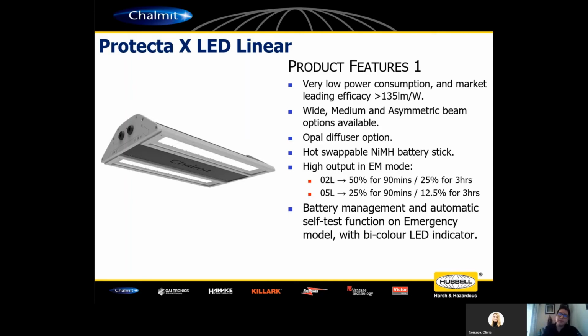The next point is regarding the emergency solution: the hot-swappable nickel metal hydride battery stick. For those unfamiliar, hot swappable means the battery stick can be changed, replaced, or maintained while the luminaire is still energized. You don't need to isolate power to access the front cover or get inside the product—you can do all this from outside the luminaire itself.